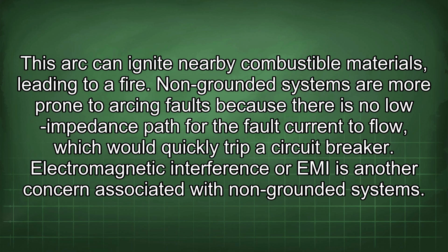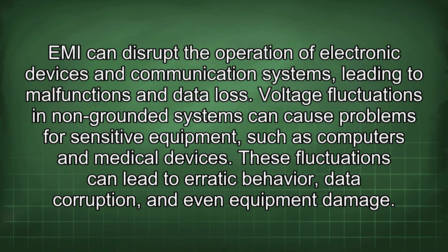Non-grounded systems are more prone to arcing faults because there is no low impedance path for the fault current to flow, which would quickly trip a circuit breaker. Electromagnetic interference, or EMI, is another concern associated with non-grounded systems. EMI can disrupt the operation of electronic devices and communication systems, leading to malfunctions and data loss. Voltage fluctuations in ungrounded systems can cause problems for sensitive equipment, such as computers and medical devices. These fluctuations can lead to erratic behavior, data corruption, and even equipment damage.